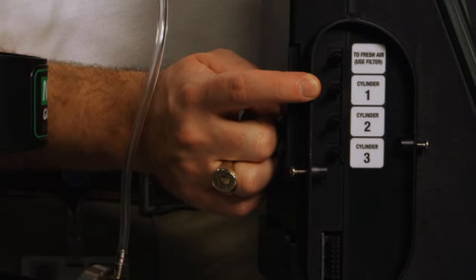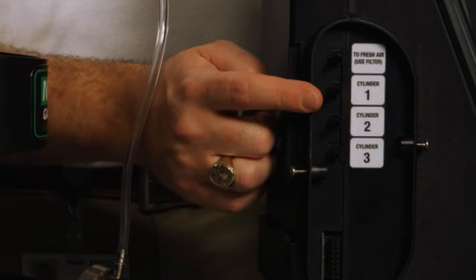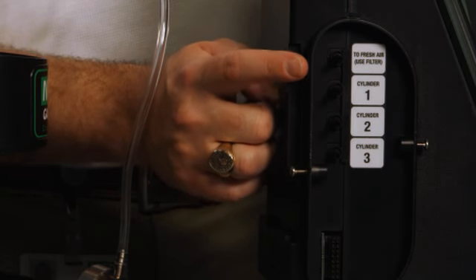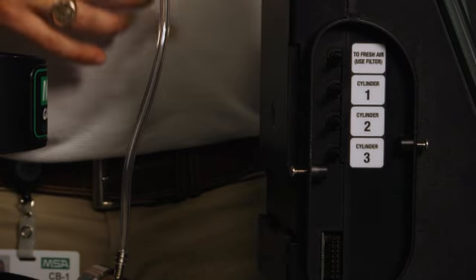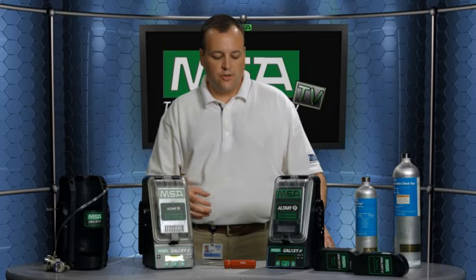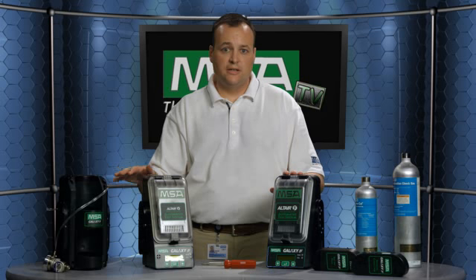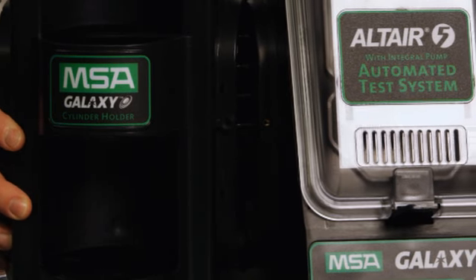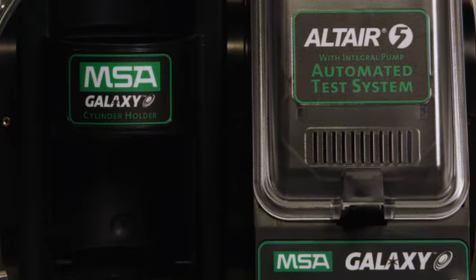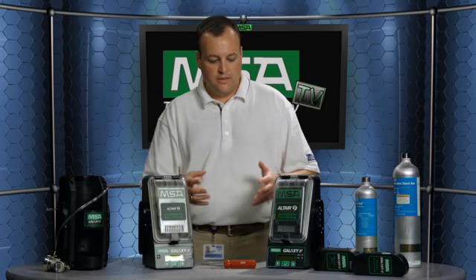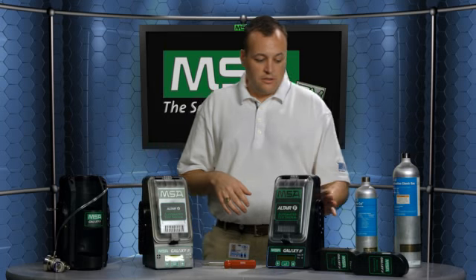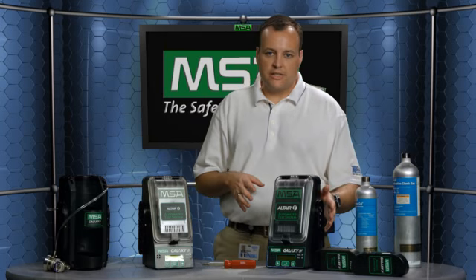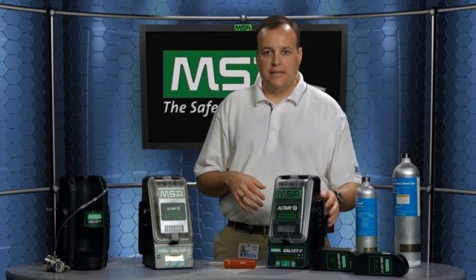There are 4 main airways or gas channels in this instrument, and what's really nice about the Galaxy is that that's all inside, so you don't have any external plumbing, tubing, things of that nature. Everything gets hooked up, and when you hook up the test stands and the gas cylinder holders together, that channel for the gas to flow through is protected by the housing of the instruments. Once you hook them together, you tighten them with a screw in the front, tighten a screw in the back, and you're basically ready to go. Your last test stand, the one that's furthest to the right, is your master test stand. It's very important that you leave the white plugs in that test stand because otherwise the gas will leak out of that side.